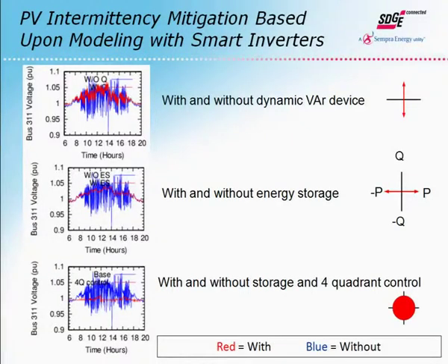Here's an example of a solution and modeling. These are electrical models of that other circuit where you've got PV system production varying significantly. In this case, we're injecting reactive power dynamically, and you can see where the 4-quadrant term comes in, operating in all 4 quadrants of the curve. A dynamic VAR device is just straight up and down on the reactive power curve.